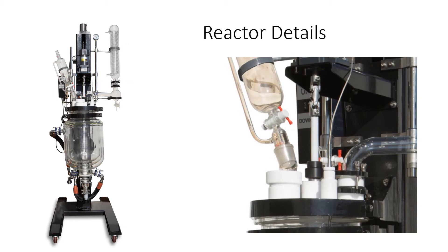Reactors are machines that allow you to control the temperature and the agitation of your sample. Let's walk through some of the different parts on it. You'll notice we have three layers on the body of the reactor. The innermost layer is where you would put your material. The middle layer is where you would circulate some fluid, which would be connected to your external heating or cooling circulation device. And the outer layer is vacuum jacketed.